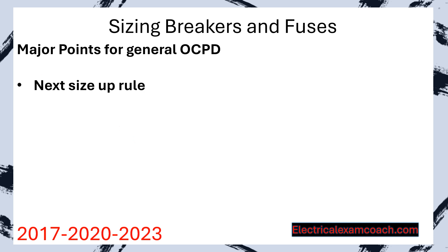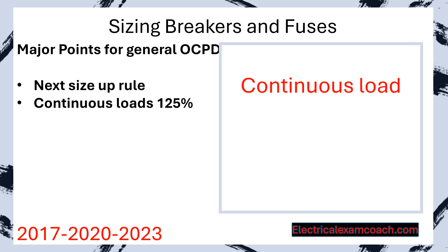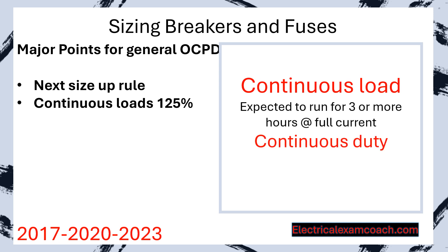The next major point is continuous loads at 125%. There are two different names you may see: continuous load or continuous duty. A continuous load is defined as expected to run for three or more hours at full current. In the exam prep world, it might say a load runs for five hours or ten hours — it doesn't matter how many hours, if it's three or more, it's considered a continuous load.